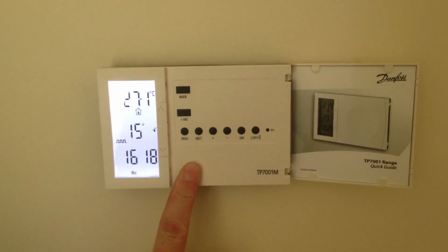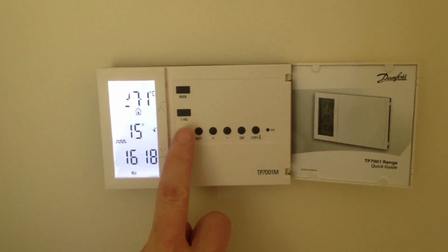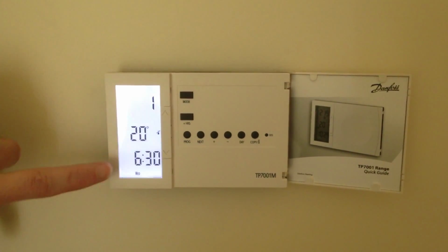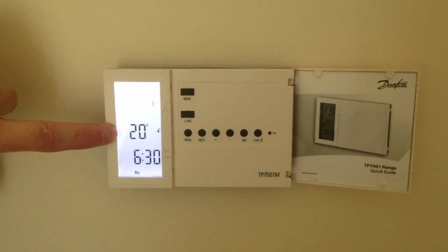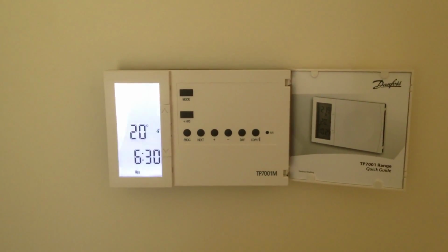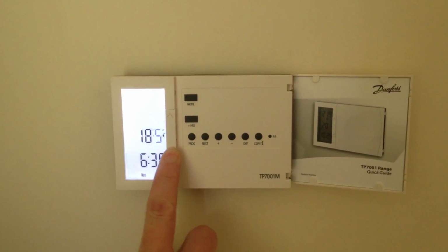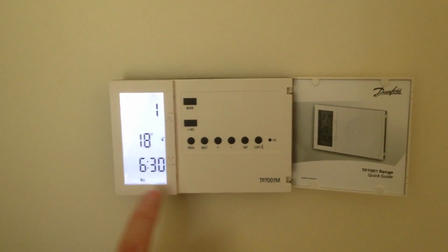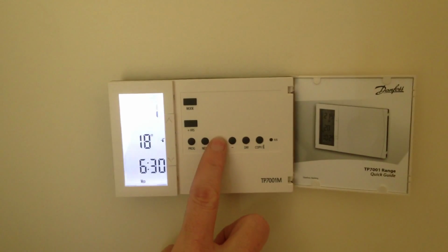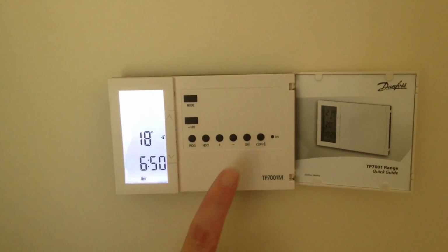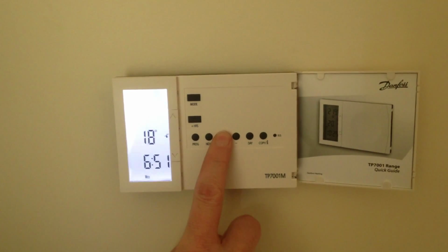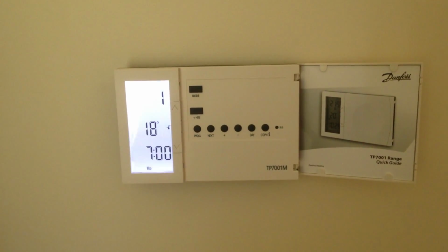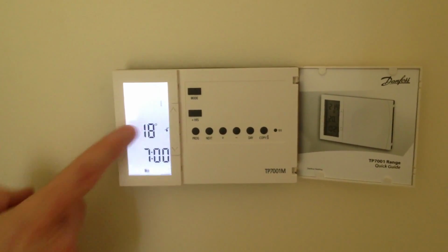To program it, to set the times and temperatures that you want it to follow, we'll press program. And we'll see the first event is our first event in the morning. So at 6:30 a.m. we want it to be 20 degrees. And this is, bear in mind, for Wednesday. If we wanted it to be lower, say you were happy with 18 degrees in the morning, you raise and lower your temperatures here, and you change your time with the plus and minus buttons. So say you were getting up a little bit later, maybe at 7 a.m., you change it here. A long press moves it on by 10-minute intervals, and short presses move it by 1-minute intervals. So now our first event is, we want at 7 a.m. it to be 18 degrees.